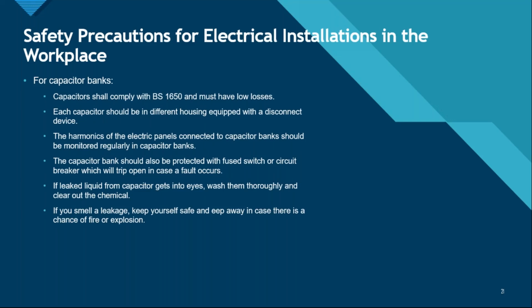For capacitor banks, capacitors shall comply with BS 1650 and must have low losses. Each capacitor should be in a different housing equipped with a disconnect device. They should have a disconnect device, like we discussed about the incident that happened before. If there are capacitor banks, they also need to be disconnected. They need to be disconnected from the entire electrical system before that electrical system is grounded, earthed, tested, or maintained.